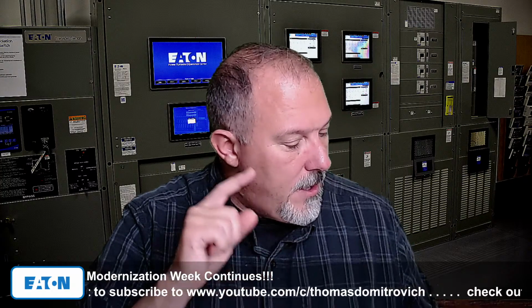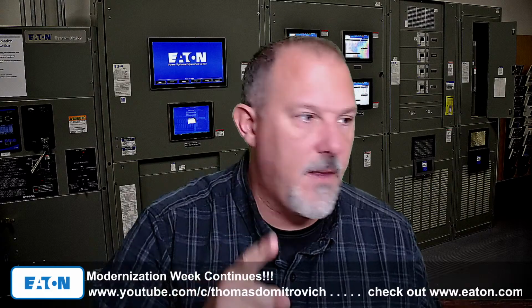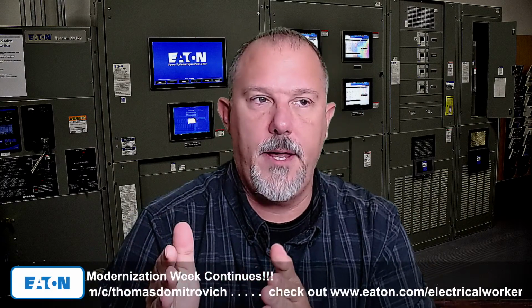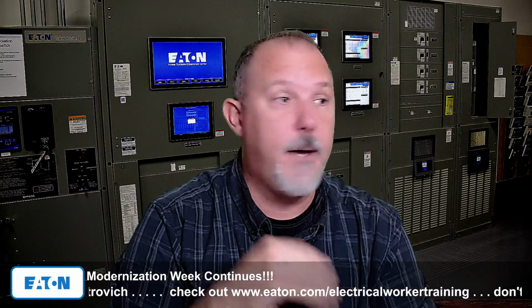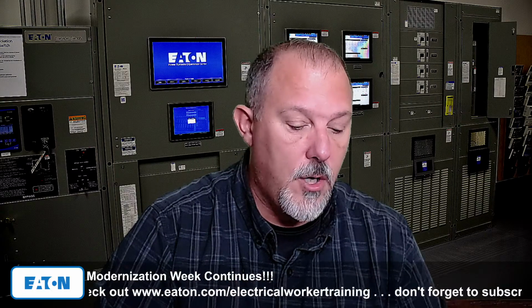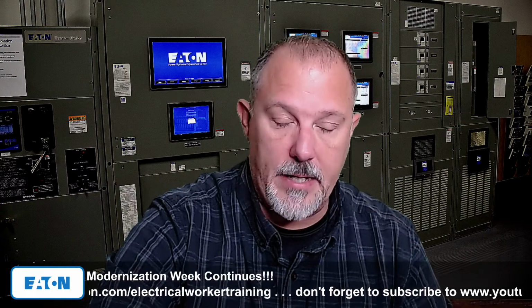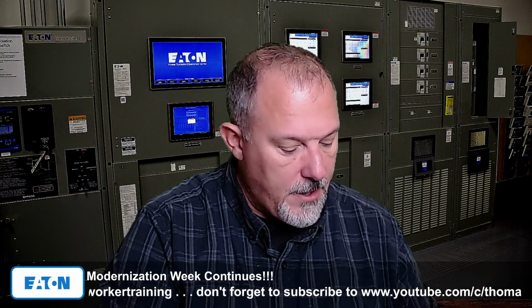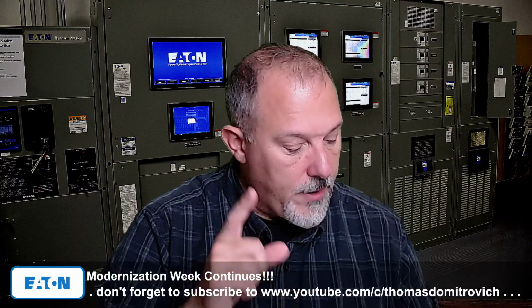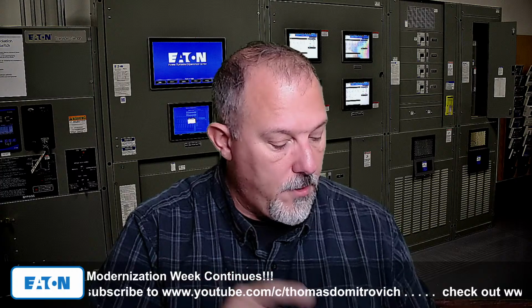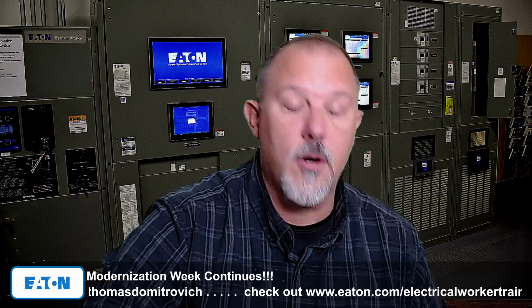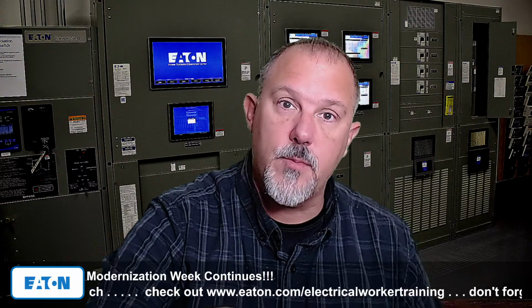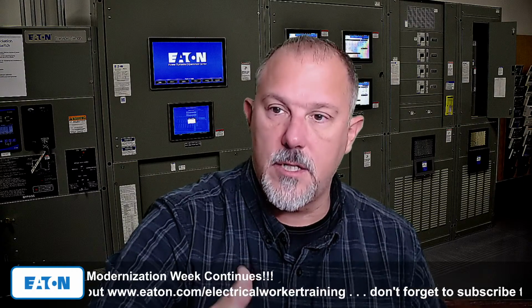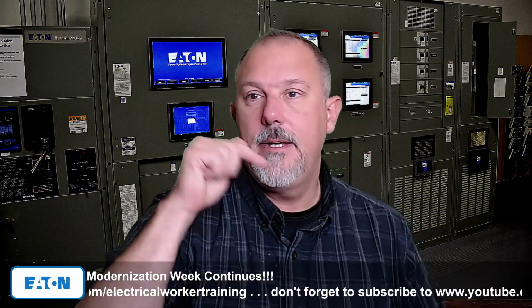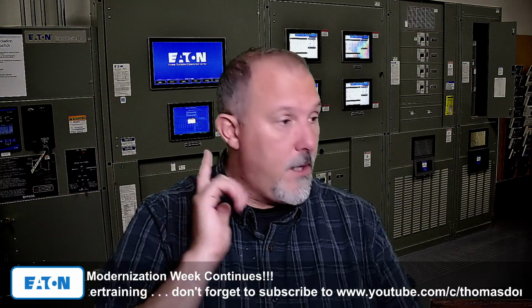So anyway. All right, so 210.52 would be, I think, the right answer that I would direct you to from a height perspective of a receptacle on the wall. Now, if you're talking about counter space, like countertops and work surfaces, there are other requirements, and those are in, again, 210.52. But I would point you to 210.52(C) for countertops and work surfaces, because there are limitations on where you can place your receptacle outlets when serving a countertop or peninsulas and all that good stuff. So be mindful of that in the list. All right. Okay.